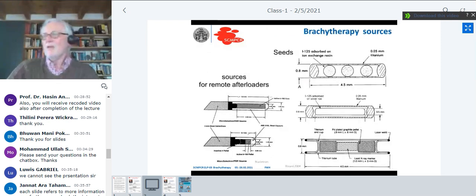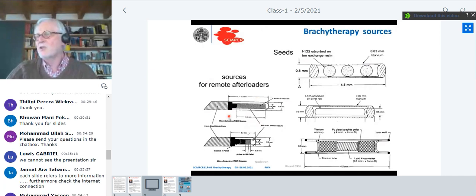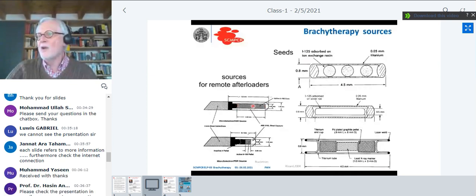This is what the sources look like. Technically, these over here are the afterloader sources. The source is always connected to a wire, inside an encapsulation, which is typically stainless steel, or maybe titanium if it's to be used in MR. Inside the encapsulation you have a wire - with the isotopes used today, it's normally a solid wire of iridium or cobalt.